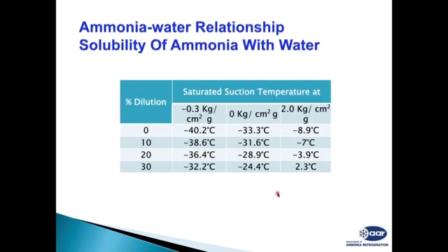Remember, I told you at the beginning, we need anhydrous ammonia of 99.95% purity. Now, if we have 10% water in a refrigeration plant, then at -0.3 kg per square centimeter, which is around -40 degree, we will get only -38 degree instead of -40. If it is 30%, we'll get only -32. So to get -40 with 10% dilution, we need to lower our actual suction pressure. It also means the ammonia temperature has gone up, so we need to lower the suction pressure. We have to operate the compressor at lower suction pressure, which costs electricity and affects the refrigeration capacity of the system.